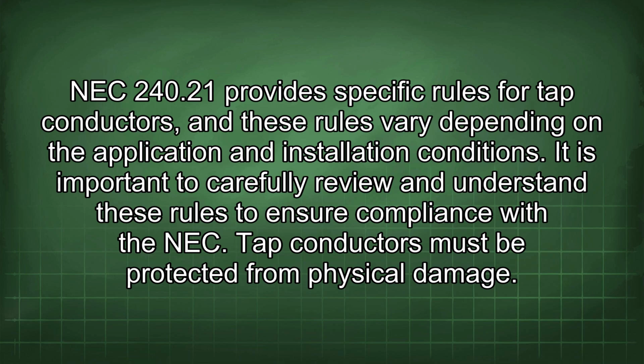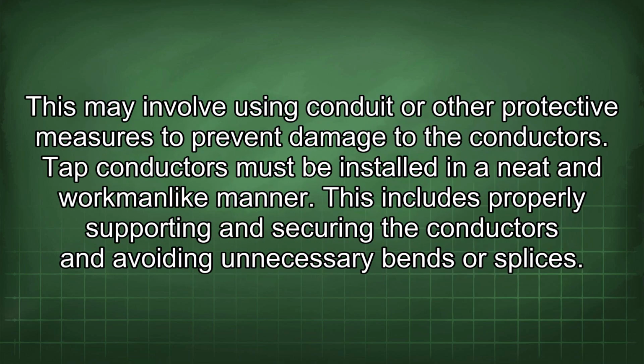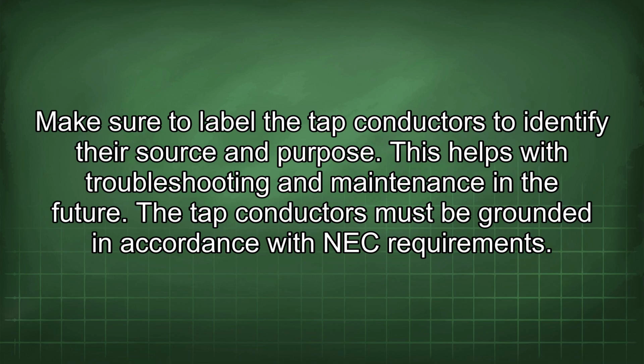Tap conductors must be protected from physical damage. This may involve using conduit or other protective measures to prevent damage to the conductors. Tap conductors must be installed in a neat and workmanlike manner. This includes properly supporting and securing the conductors and avoiding unnecessary bends or splices. Make sure to label the tap conductors to identify their source and purpose. This helps with troubleshooting and maintenance in the future.